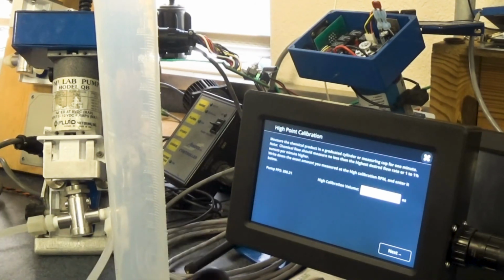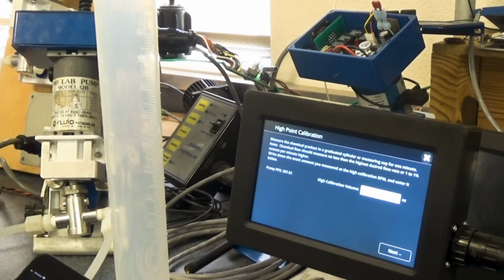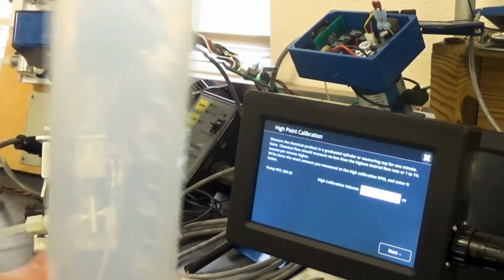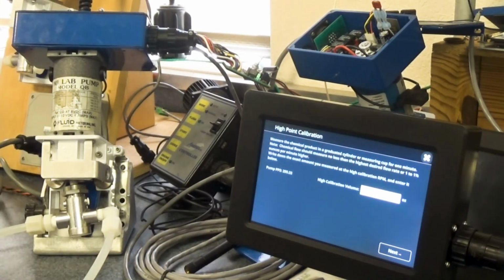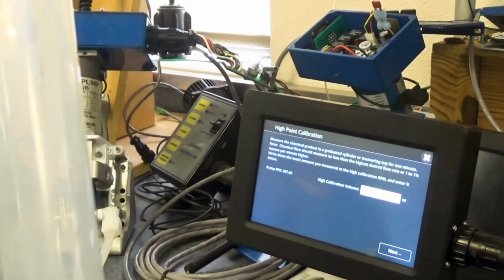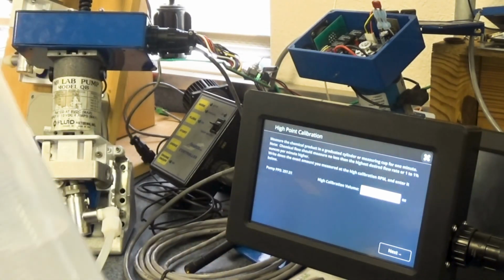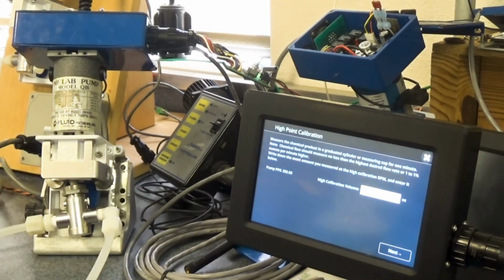So what we need is a clock, and we're going to measure the flow for 1 minute coming out of the nozzle or out of the tube that we're measuring here. So let's start the counter and measure with our graduated cylinder. So we just let her fill up. As you can see right here, we have a pulses per second gauge. This is to indicate the actual RPM or pulses per second that the FMI pump is doing.